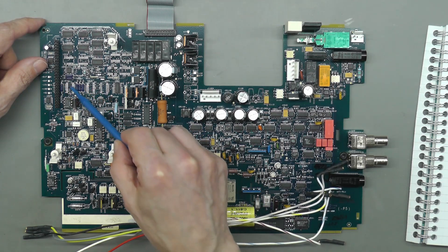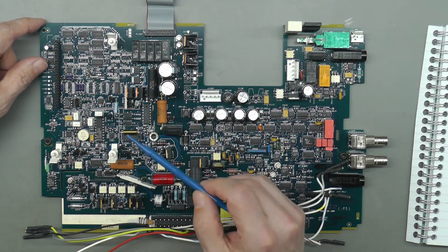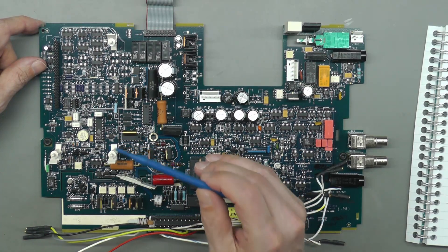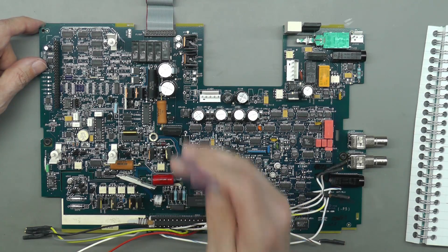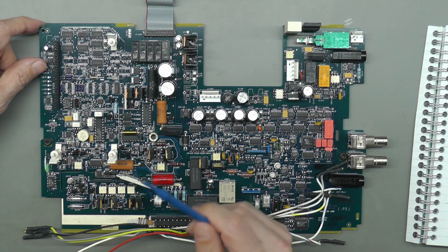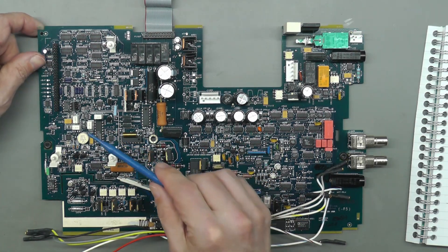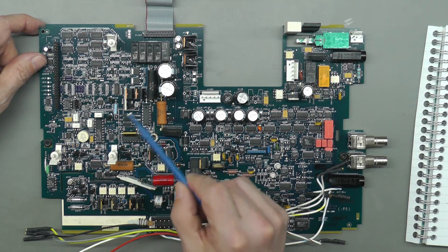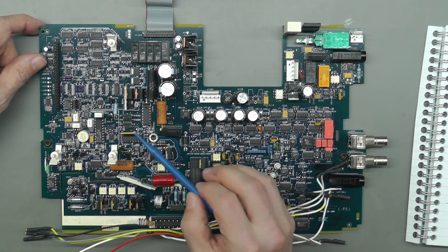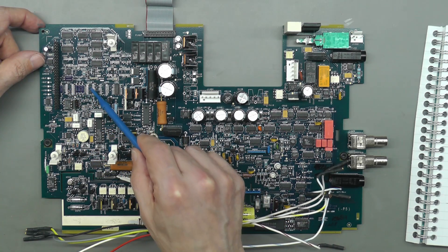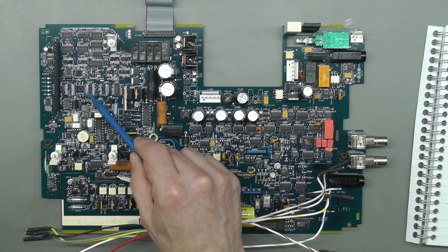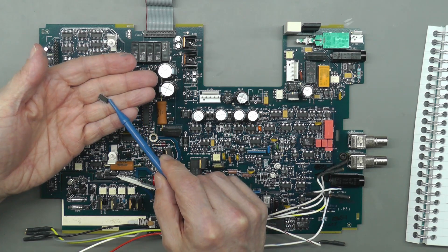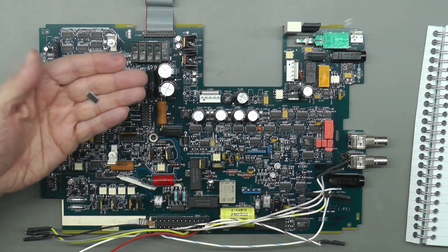I've removed those three DG211s, and the resistance across the minus 15 and plus 15 has now both gone to 4 ohms. That is, the plus 15 volt rail as well has gone to 4 ohms, so I think I'm on the right track that there's a device or devices that have a common plus and minus 15 volt supply that's shorted internally and causing this. Looking at one of the DG211s, this one in particular, the U319, measuring the actual chip itself across the minus 15 volt rail down to ground, it's 2 ohms. We're definitely on the right track.